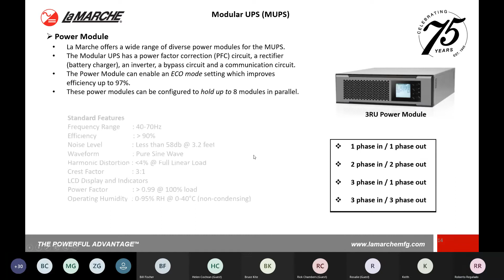Moving on to some of the power modules of the modular UPS. As a standard feature, they all have that frequency range. I'm not showing the voltage ratings here because that is dependent on your power module. But as a standard, they all have that automatic sensing of frequency range of 40 to 70 hertz. So your typical 50 or 60 hertz applications is not going to be anything special you have to request. Efficiency over 90% depending on the mode of operation. Your noise level is 58 dB. Pure sine wave inverter, harmonic distortion less than 4% at full linear load, crest factor, typical inverter numbers that you do want to see in the market, correct?